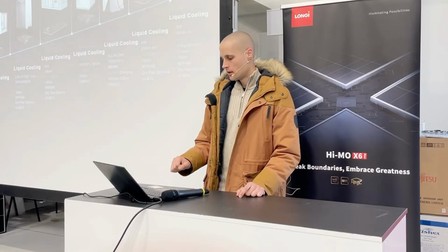For the bigger brother, it's the NRC Plus, a standardized 20-feet container with 4 megawatt hour capacity. You can also deduct the capacity if you're using smaller cells — it's going to be roughly 3.8 if you use the 285 ampere hour cells. They have two types of cells because the 306 ampere hour cells are for half C charging and discharging, while with the smaller cell you can reach 1C charging and discharging capacity.